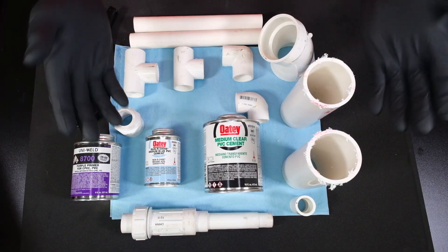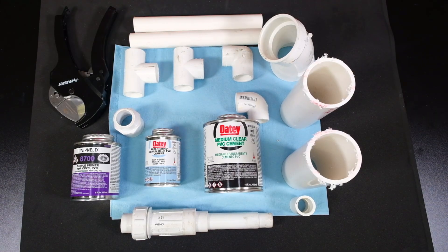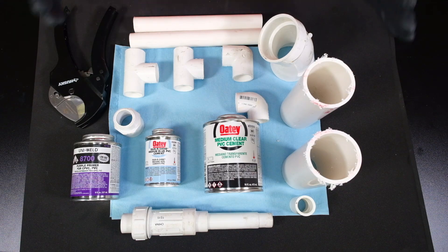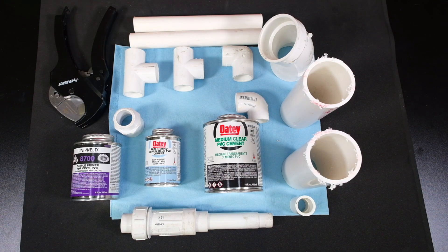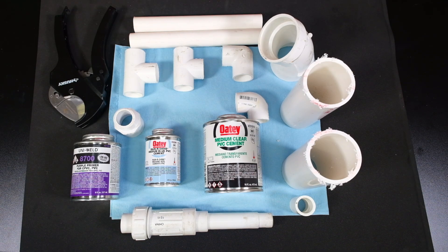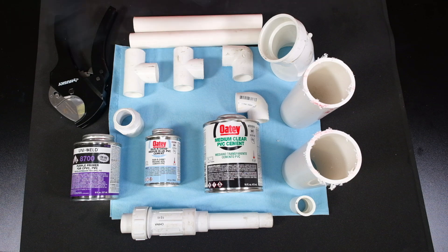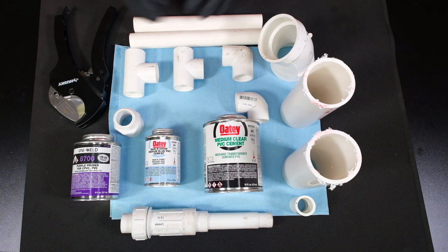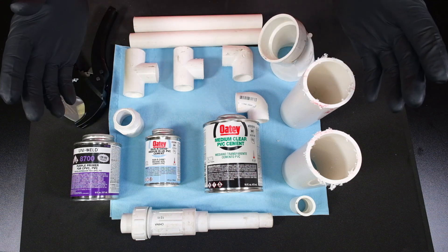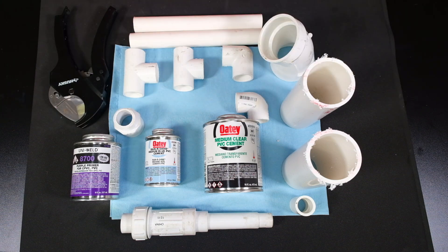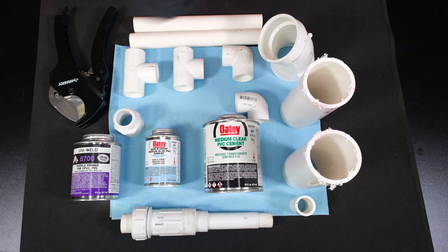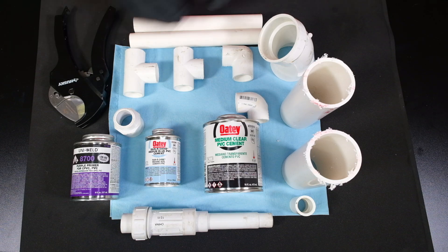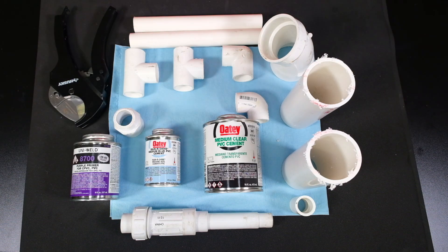Here we have PVC fittings and PVC solvent weld cement. We've had other videos that talk about CPVC and PVC. This is PVC, polyvinyl chloride, whereas CPVC is chlorinated polyvinyl chloride. PVC is not rated for hot water. CPVC is rated for hot water. CPVC is a more tan gold with gold stripe on it, and as you notice PVC is white pipe.